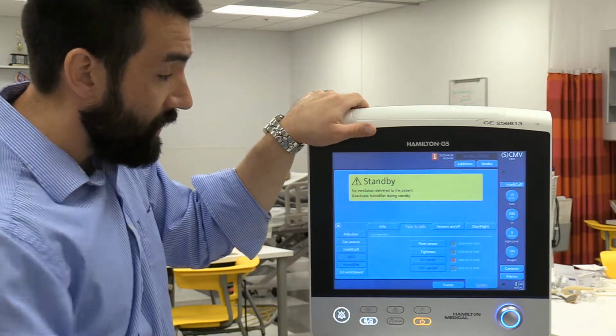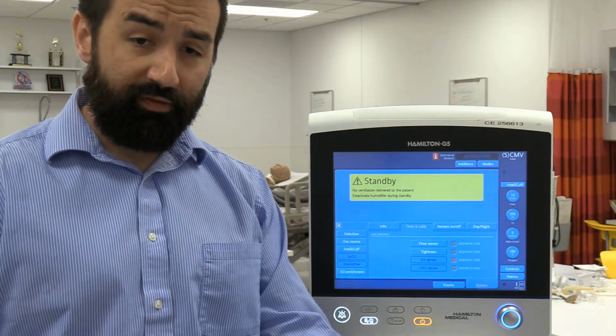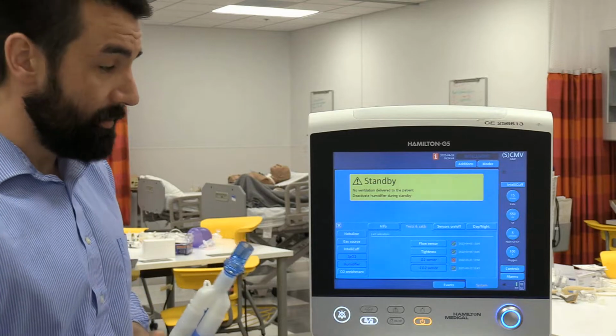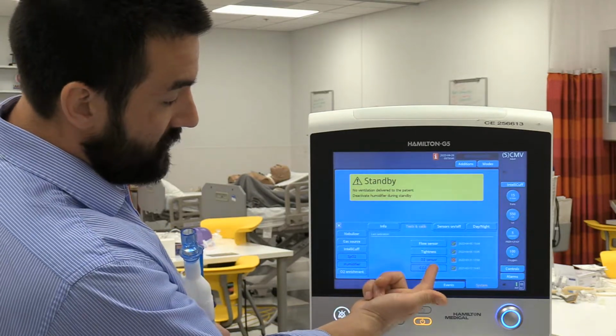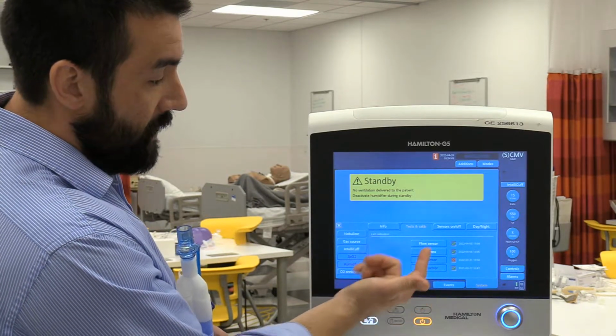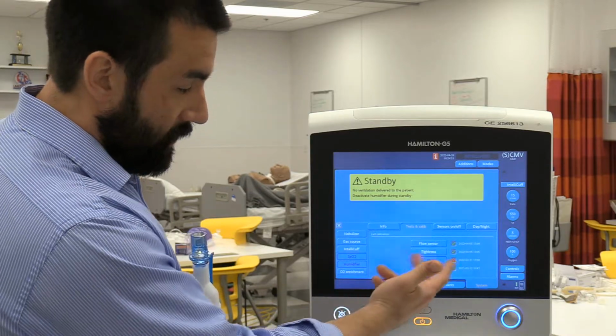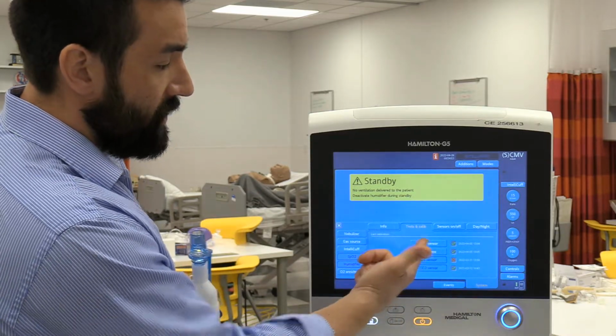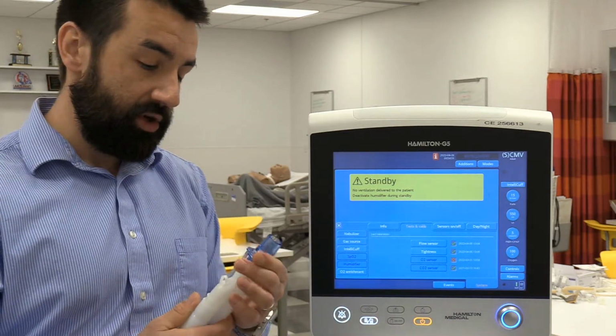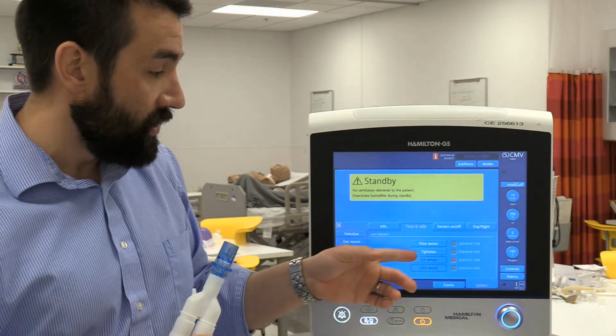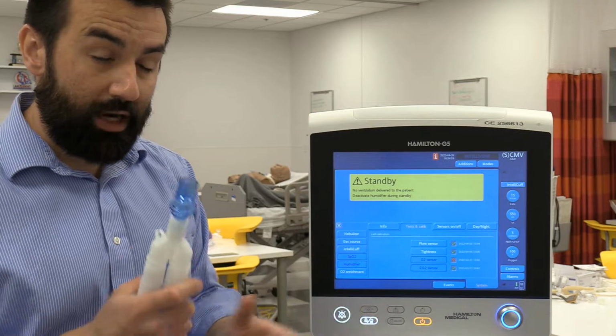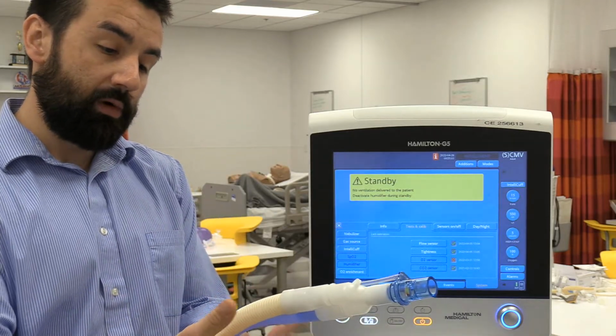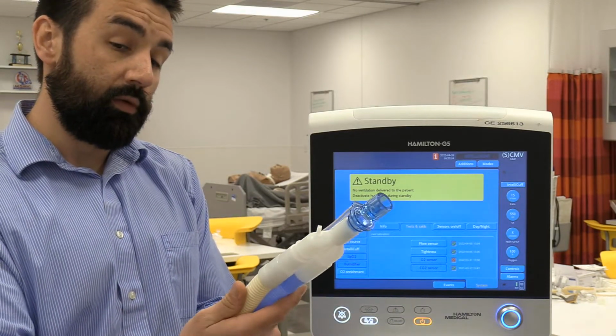I'm going to go to pre-op check here. So right now I'm running off fake oxygen, so I have our O2 sensor disabled. So you're not going to see the oxygen sensor pre-use test pop up. Usually that would be lit up and enabled. I'm going to check the flow sensor, so I'm going to zero the flow sensor, make sure everything's worked out, make sure this thing's calibrated and functional. And I'm going to do a tightness check, which is checking for a leak, and that's where we're also compensating for the tubing compliance here.